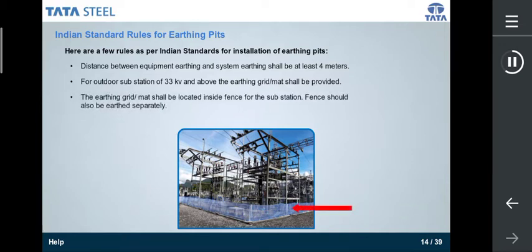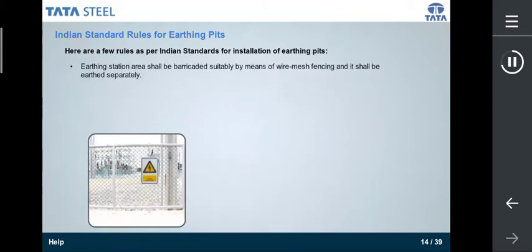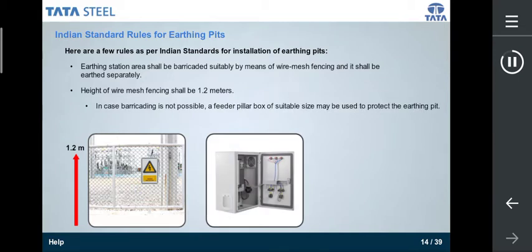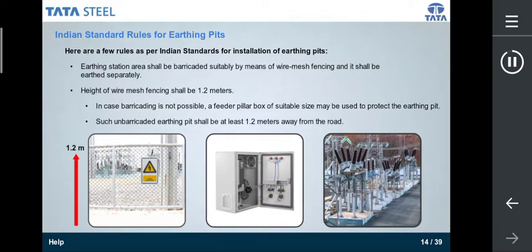The earthing grid or mat shall be located inside the fence for the substation. The fence should also be earthed separately. Earthing station area shall be barricaded suitably by means of wire mesh fencing and it shall be earthed separately. The door and fencing should be earthed. Height of wire mesh fencing shall be 1.2 meters. In case barricading is not possible, a feeder pillar box of suitable size may be used to protect the earthing pit. Such unbarricaded earthing pit shall be at least 1.2 meters away from the road. So these are the rules for installing earthing pits.